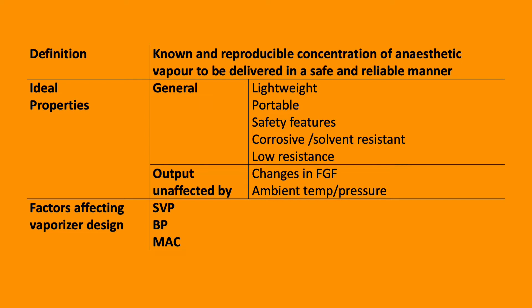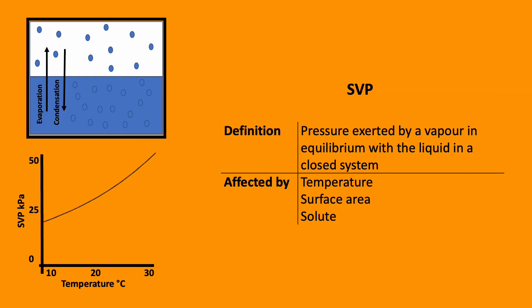What factors should affect the vaporizer design? This is based on the volatile's SVP, boiling point, and MAC. Saturated vapor pressure is the pressure exerted by a vapor in equilibrium with a liquid in a closed system. It's affected by the temperature of the system, the surface area of the liquid, and the solute in the liquid.